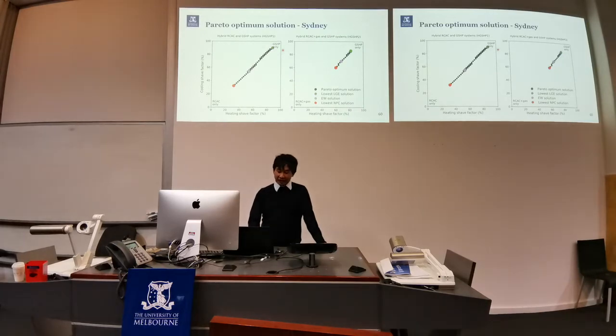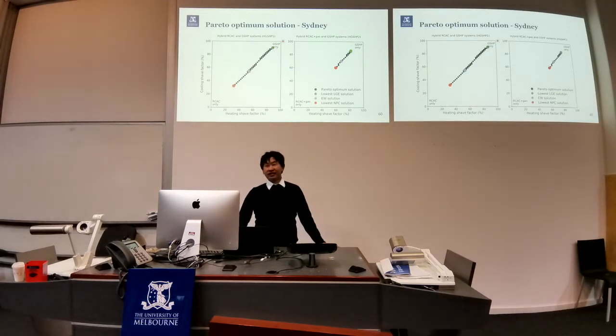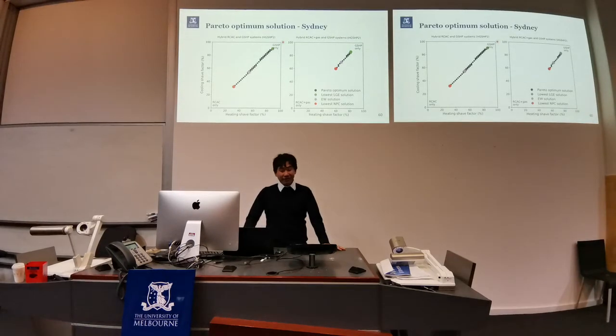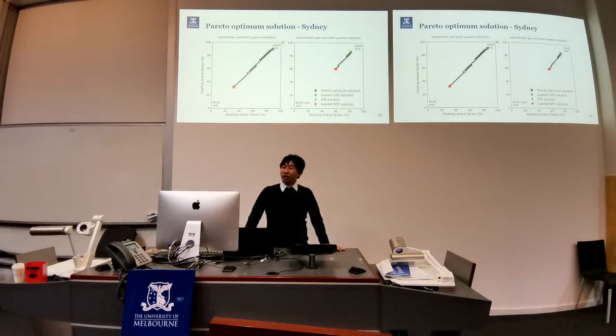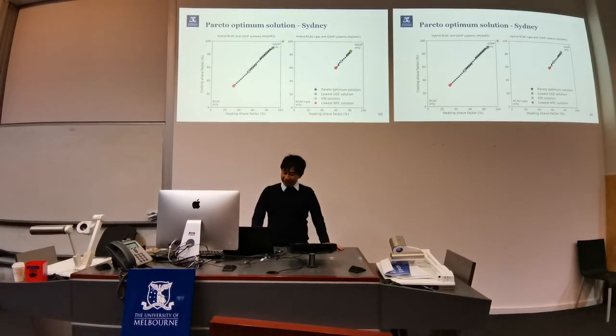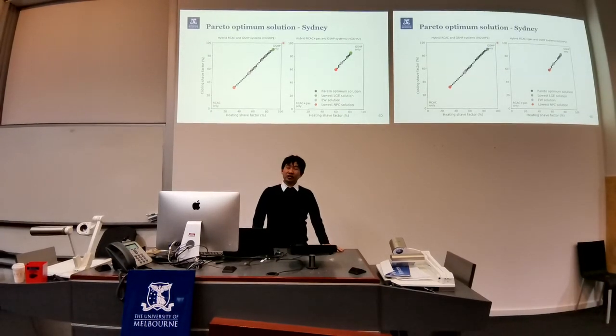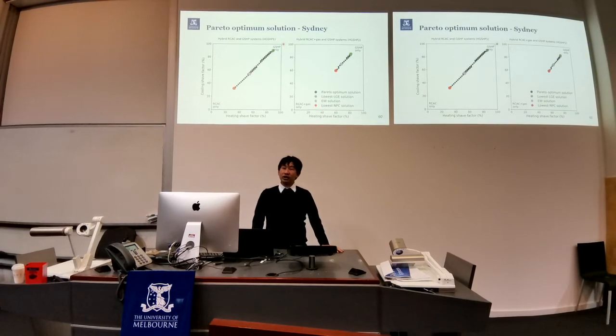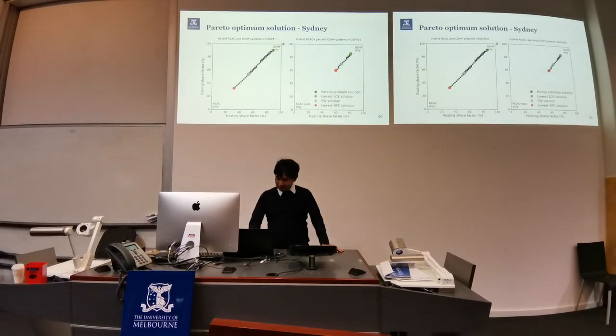One further observation: the lowest emission point is actually slightly lower than the full ground source heat pump system at 100% share factor. Now this is interesting, because the ground source heat pump system should be the most efficient. So if you want to save emissions, you should install at this point. However, at 100% this means that the ground source heat pump and the ground heat exchanger will need to be sized to meet the full thermal load. In this case, you will require a very long ground heat exchanger.